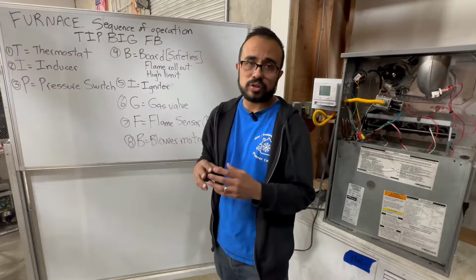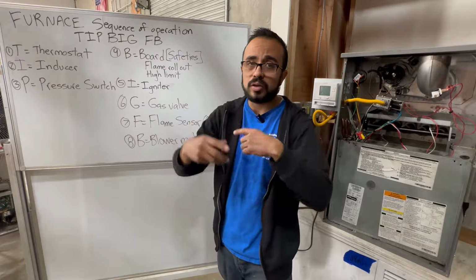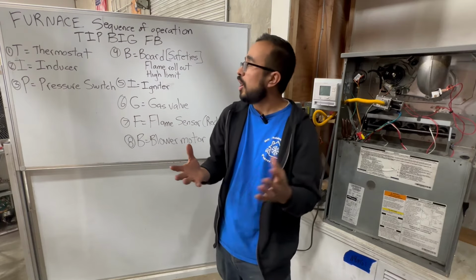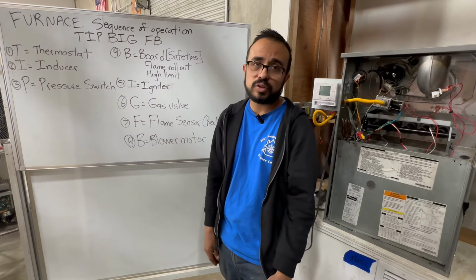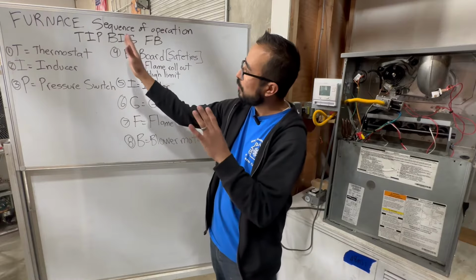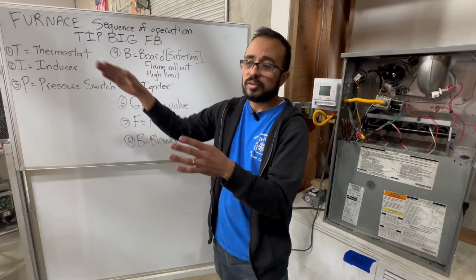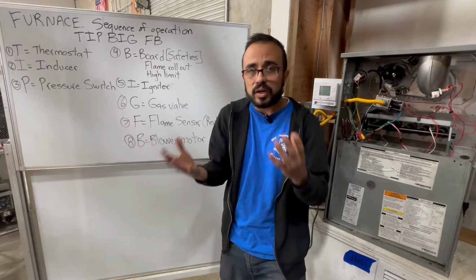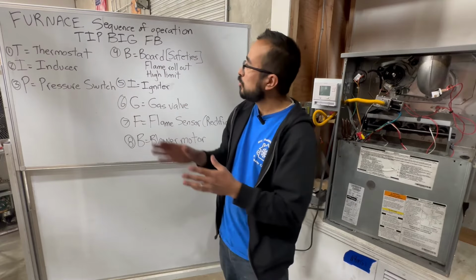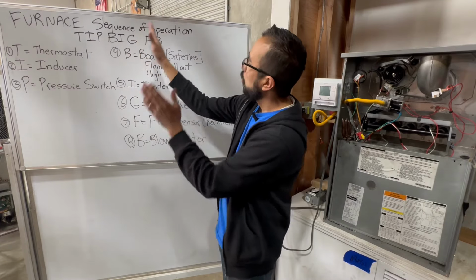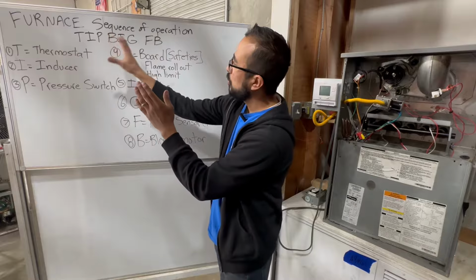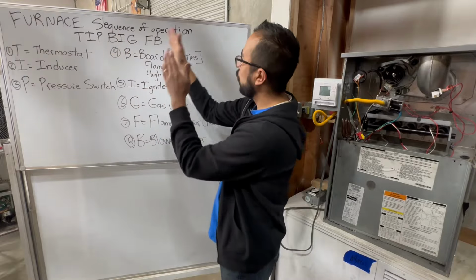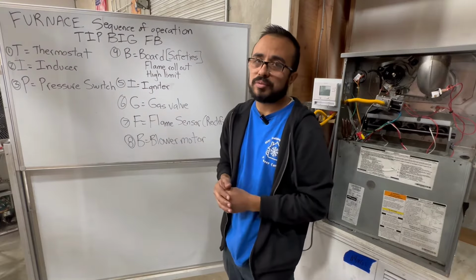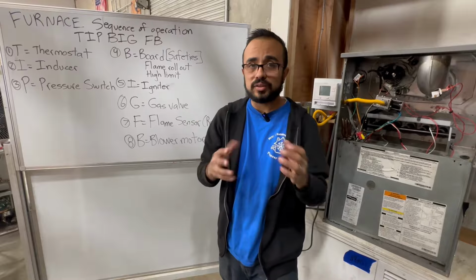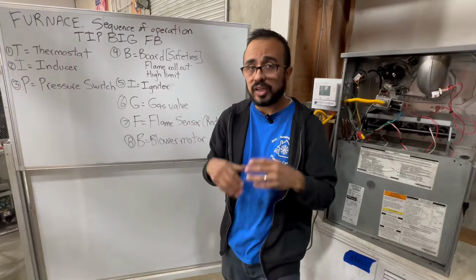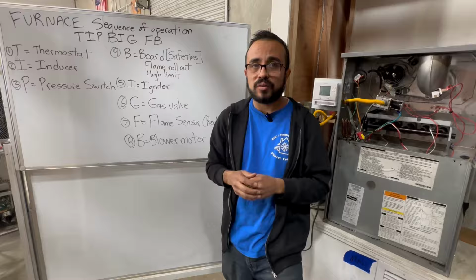Let's say your pressure switch, the inducer draft motor turns on, your pressure switch is still open. Are you going to check if your gas valve is receiving 24 volts? No, you're going to focus on the previous step to see if the inducer draft motor is pulling enough suction pressure. So wherever you're at, don't work forward, work backwards to see what's going on before you start working forward on the steps. And that's at least how I like to approach the acronym. It has helped me a lot when troubleshooting furnaces.